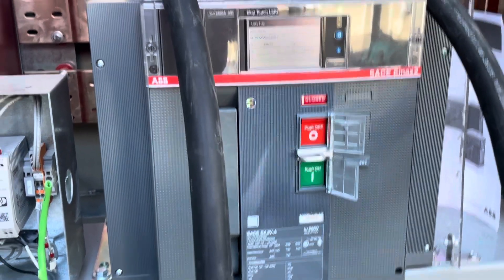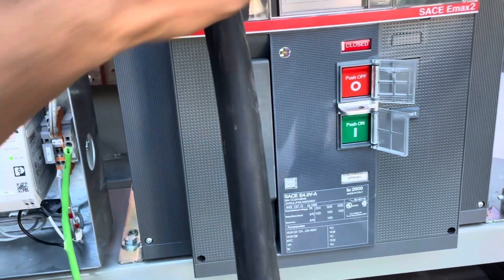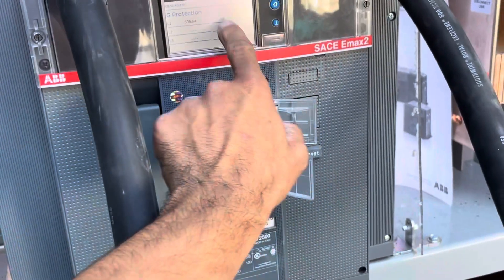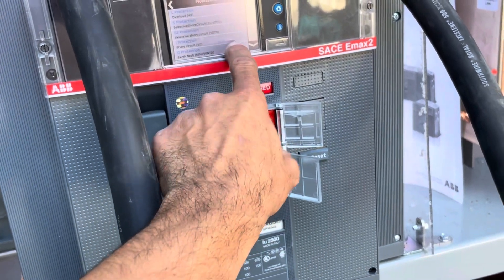As you can see, I got an ABB breaker type SACE with the EKIP Touch LSIG trip unit — nothing too fancy. So I'll go to home here, there we go, and I'll go to my protections, then to my ground fault protection.